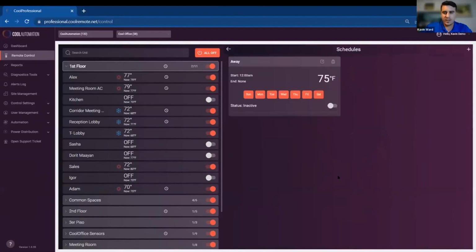Simply clicking on the schedule, it looks like we have an away schedule where at midnight every day the fan coils will all go to 75 degrees. Just ensure that it's active, and now at midnight, all of these will set back to 75 degrees.